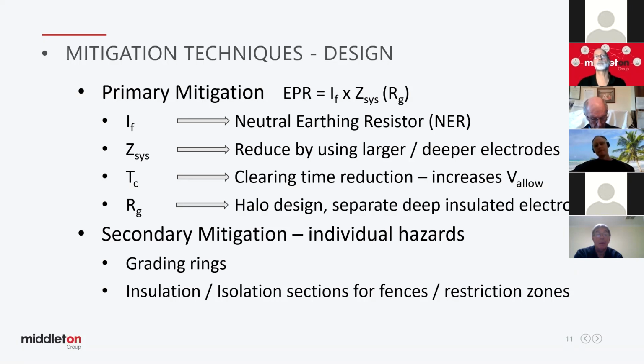So these are all primary mitigation techniques, where if we fix the EPR or get the allowable above the touch voltages we've measured, we fix them all in one go. We do a primary mitigation. However, that's not always going to work. It might fix most of our problems, but you might find there's one or two little problem situations that aren't fixed that way. So we can do a secondary mitigation.